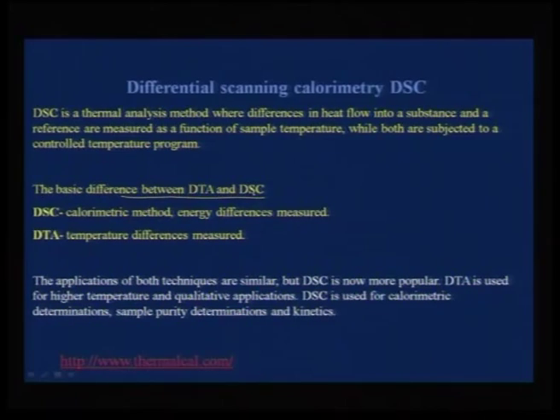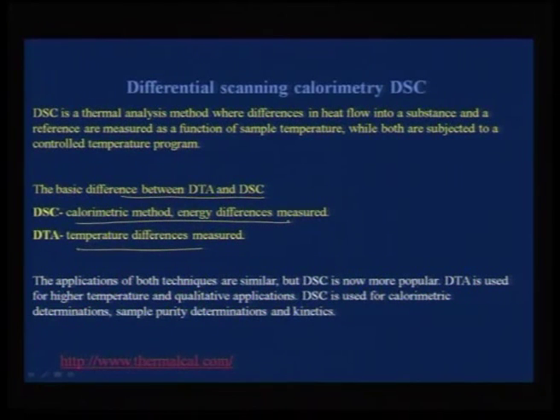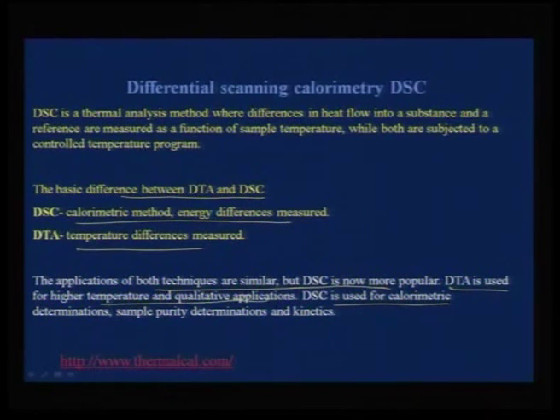Now I will discuss some issues related to differential scanning calorimetry, where you can quantify more results. The basic difference between DTA and DSC: in DTA, temperature differences are measured, whereas in DSC, the heat flow from or out of the system is measured. Applications are similar, but DSC is more popular because it gives understanding of heat exchange, while DTA is conveniently used for very high-temperature measurements.